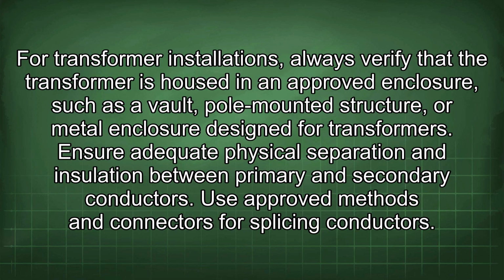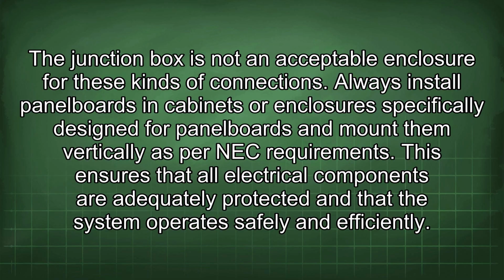For transformer installations, always verify that the transformer is housed in an approved enclosure, such as a vault, pole-mounted structure, or metal enclosure designed for transformers. Ensure adequate physical separation and insulation between primary and secondary conductors. Use approved methods and connectors for splicing conductors. The junction box is not an acceptable enclosure for these kinds of connections. Always install panel boards in cabinets or enclosures specifically designed for panel boards, and mount them vertically as per NEC requirements. This ensures that all electrical components are adequately protected and that the system operates safely and efficiently.